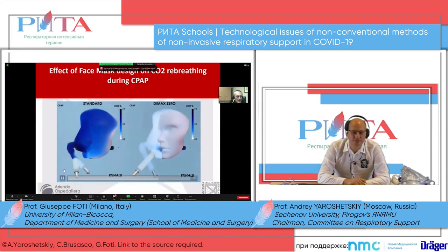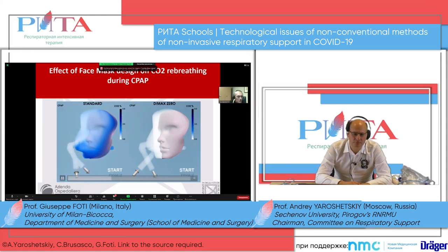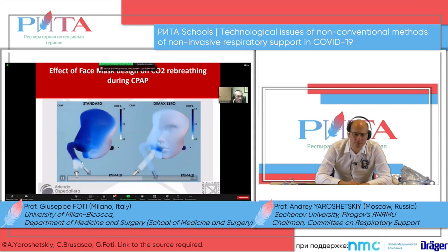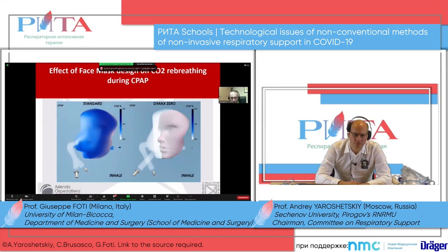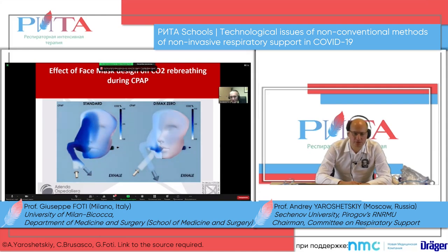Yes, perfect. Here the flow is the same, around 90 liters per minute. But with this system, during expiration, the flow goes from here to here, see, hop hop hop hop. So instead here, during expiration, the flow goes inside the mask and comes out from the other side. So the CO2 the patient is expiring is washed out from the mask, and this decreases the dead space of the mask.